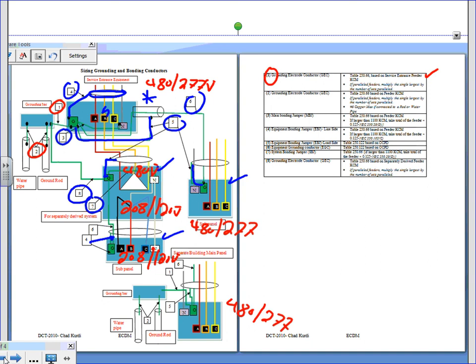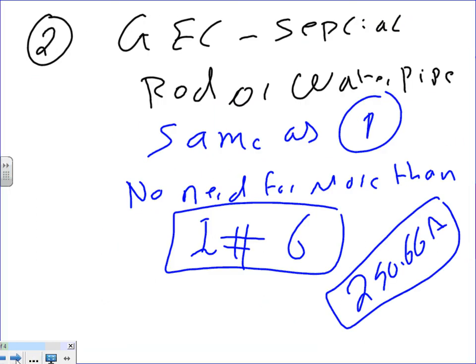That one is going from the switchgear to a ground bar on the wall, which is why we size it directly based on 250.66. The second one, going from the ground bar to a pipe, uses the same table, but there's an exception in the code that says if you're tying to a rod or a pipe, you don't have to go higher than number 6. Everybody's seeing that? Just a special condition for these 2. You don't have to go higher than number 6.